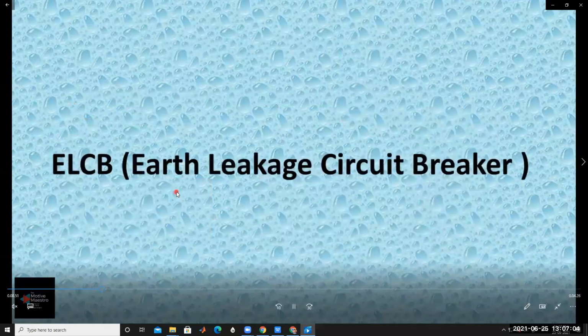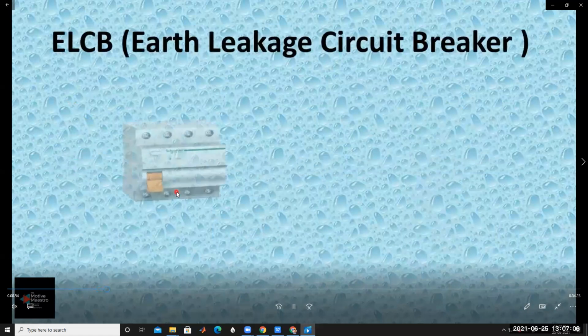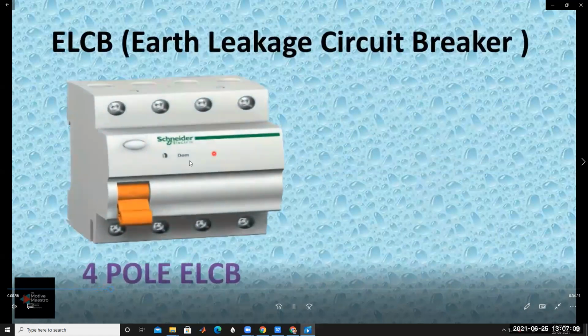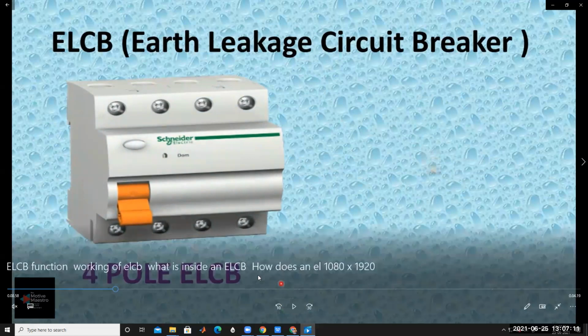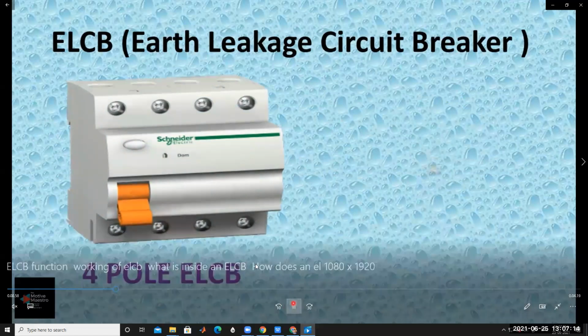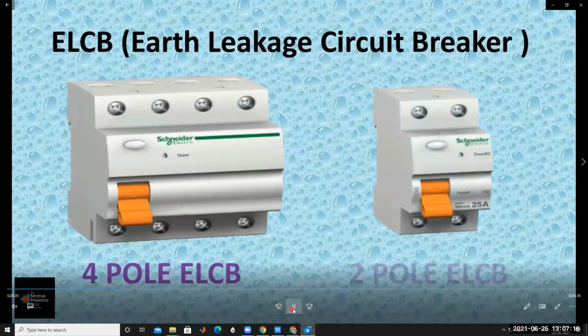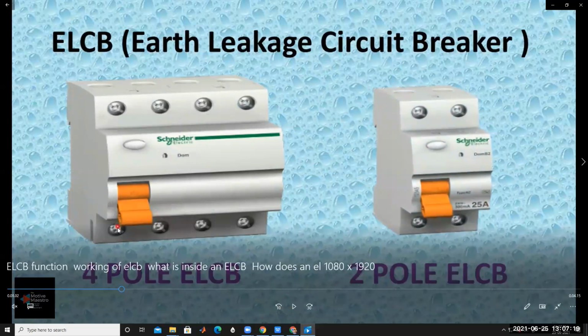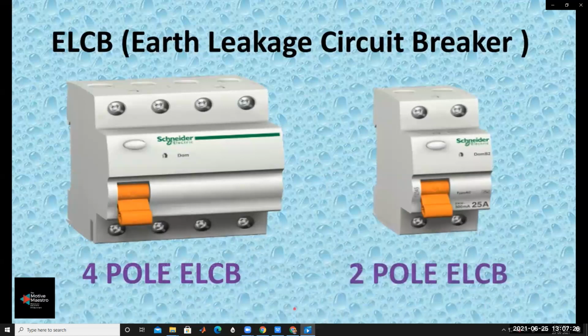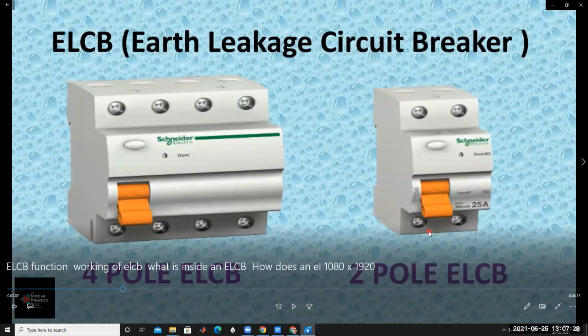And then the earth leakage circuit breaker can be used to protect. There are different types of earth leakage circuit breakers. This is a 4-pole earth leakage circuit breaker. Here there are 1, 2, 3, 4 poles, that's why it's called a 4-pole earth leakage circuit breaker. This one is only a 2-pole earth leakage circuit breaker. Its operating range is 25 amps. According to our requirement, 4-pole or 2-pole earth leakage circuit breakers are used.